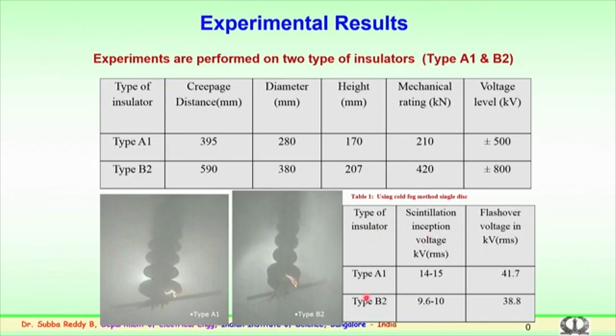So, these are some of the values which have been obtained, say in the case of a 395 creepage distance. The inception of the scintillations, the inception of the arcs, what we call these discharges, the starting point of these discharges, was anywhere between 14 to 15 kilovolts, and the flashover was 41 or 40, nearly around 42 kilovolts, for these discs tested using the cold fog method. The cold fog method is very clearly explained in the standard 1245.